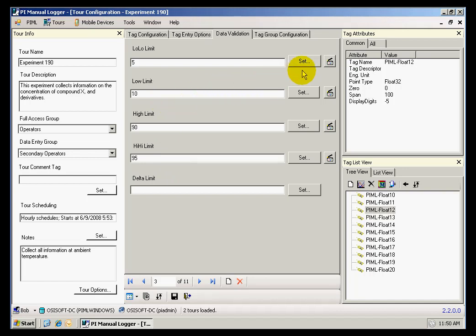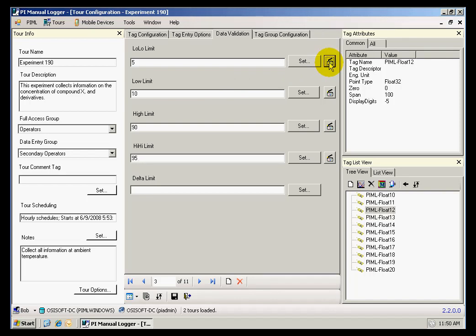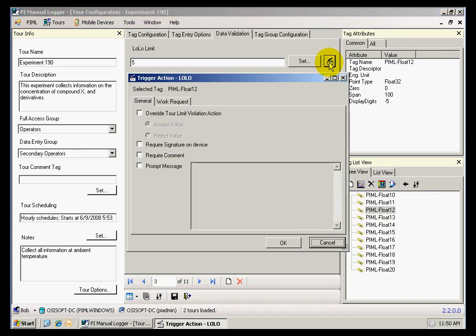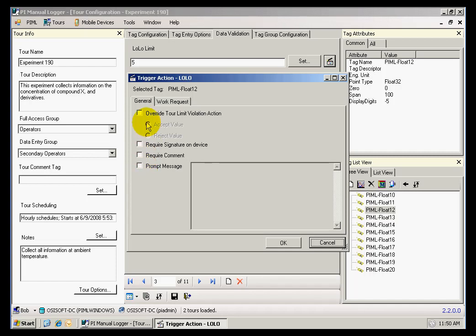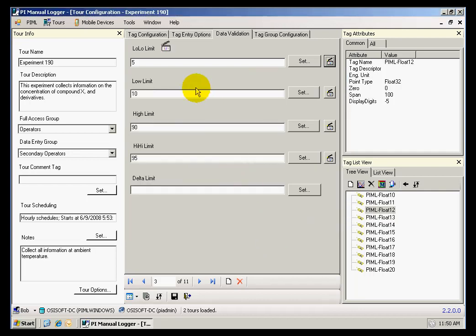I also have an option of specifying actions when these limits are violated. Some of the options that are available include requiring a signature when the limit is violated, or requiring a comment, or prompting a specific message. In this case, I'm going to specify for the low low limit a message to call the control room. So when I enter data, if the value is below 5, I will receive a message that says to call the control room.